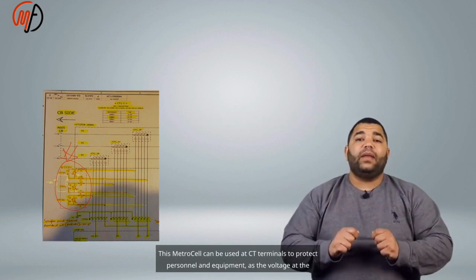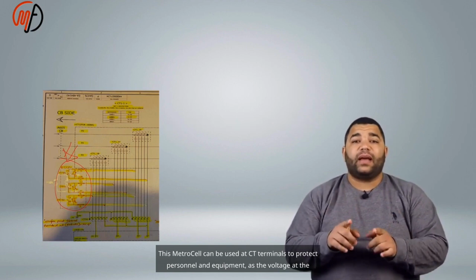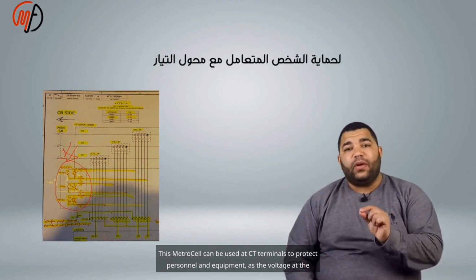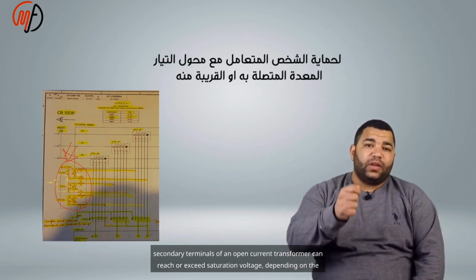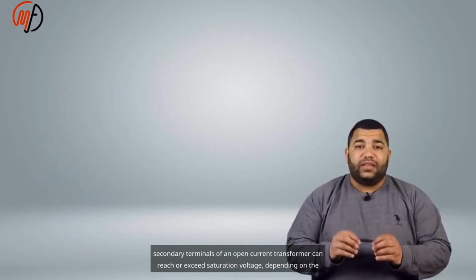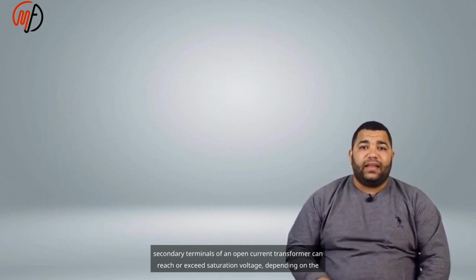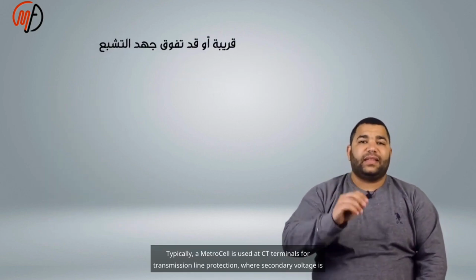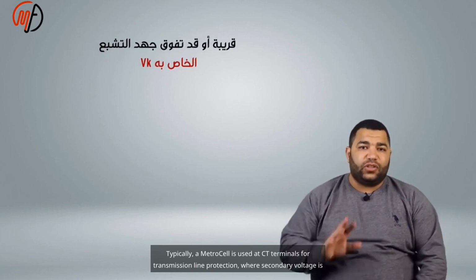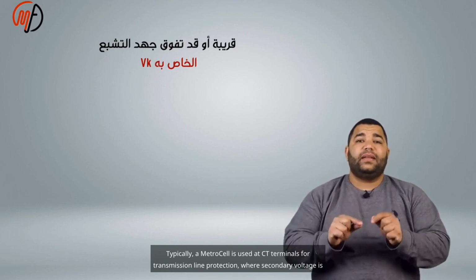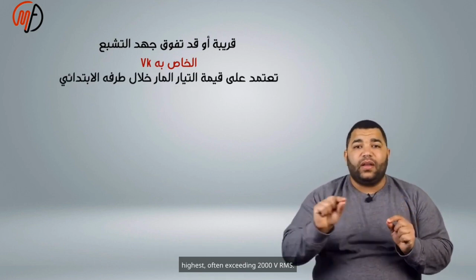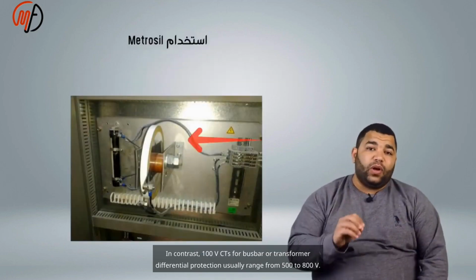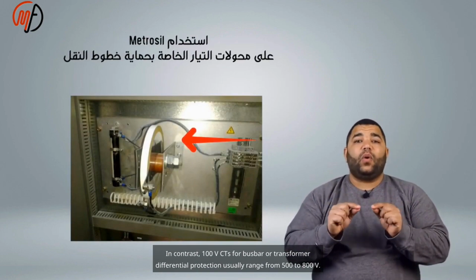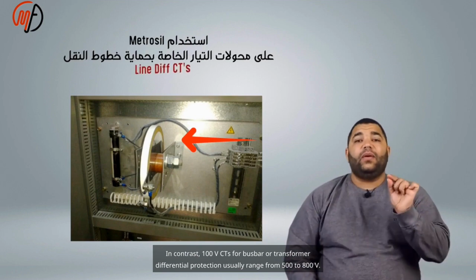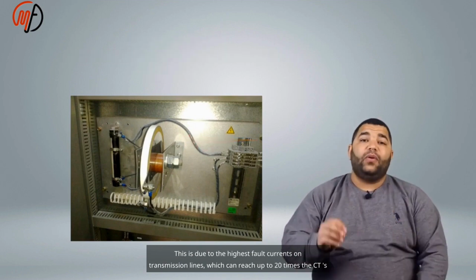This Metrosil can be used at CT terminals to protect personnel and equipment, as the voltage at the secondary terminals of an open current transformer can reach or exceed saturation voltage, depending on the primary current. Typically, a Metrosil is used at CT terminals for transmission line protection, where secondary voltage is highest, often exceeding 2000 V RMS. In contrast, CTs for busbar or transformer differential protection usually range from 500 to 800 V.